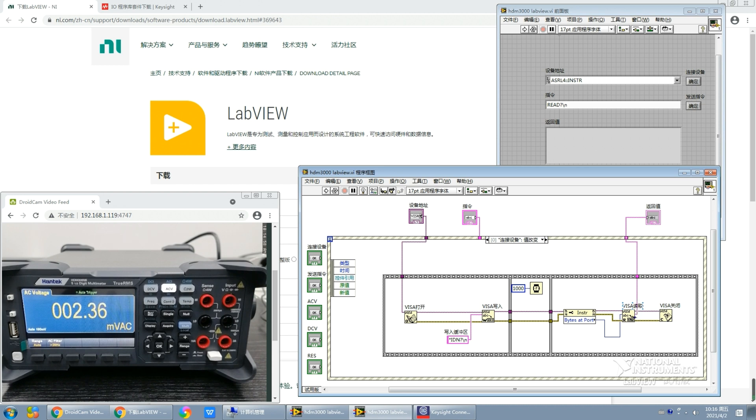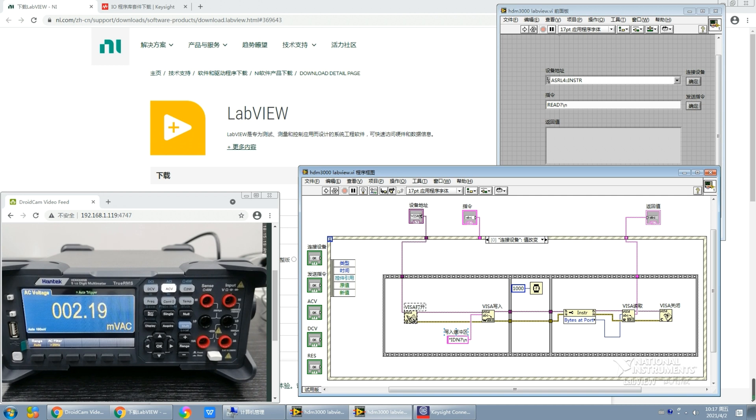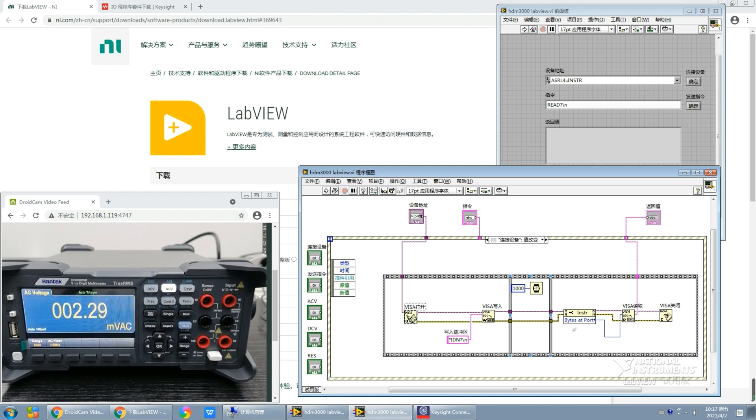One more thing needed to be noticed: each execution is followed by a VISA close function. This is of great importance because each time we execute the VISA open function, there will be a resource occupied in the resource manager. If we don't close them, we will end up with resource exhaustion. In that case, you need to reconnect to the USB or serial interfaces. So I strongly recommend you use VISA close function each time. This is all about the connect to devices event.